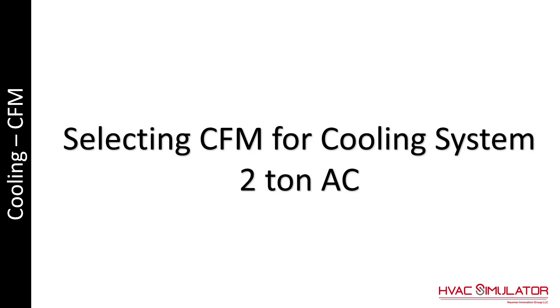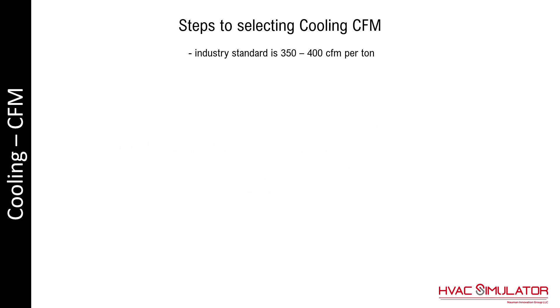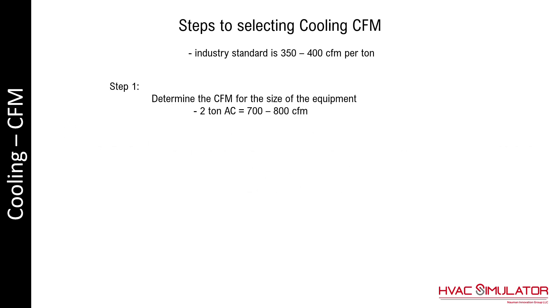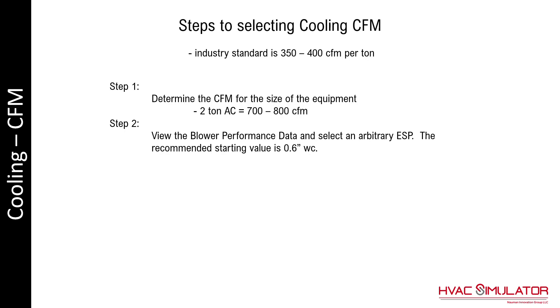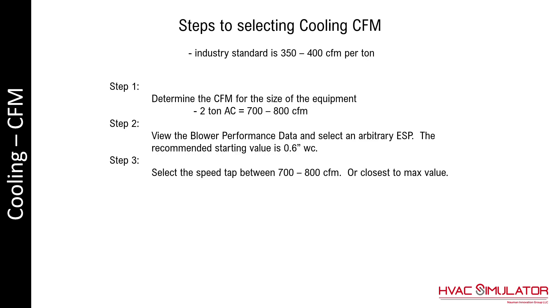A 2-ton AC will be used for this example. The steps to selecting cooling CFM: the industry standard is 350 to 400 CFM per ton. Step 1 is to determine the size of the equipment — this example is a 2-ton AC, therefore the CFM will be between 700 and 800 CFM. View the blower performance data and select an arbitrary external static pressure; the recommended starting value is 0.6 inches of water column. Select the speed tap between 700 and 800 CFM, or the closest to the max value.